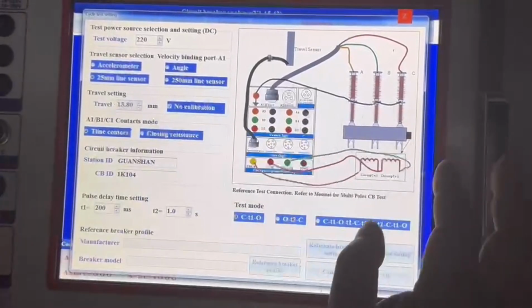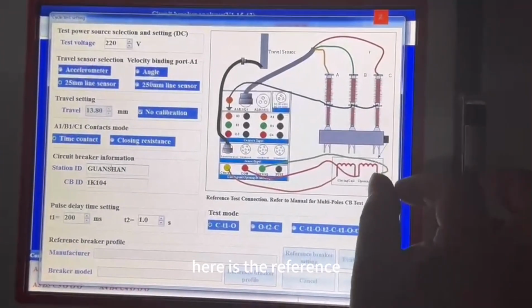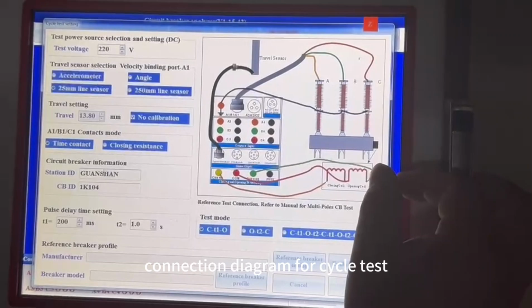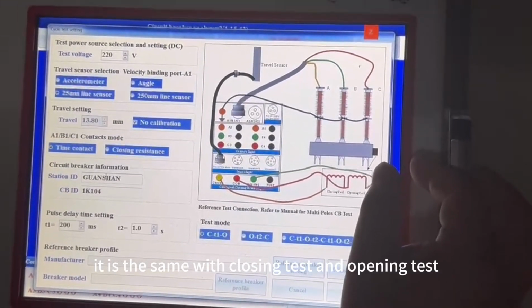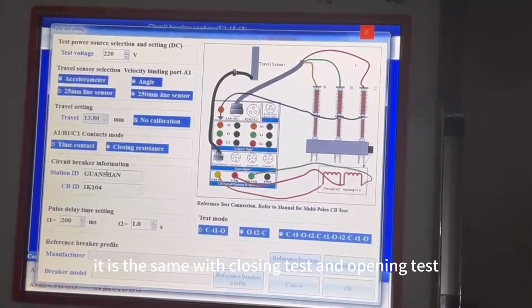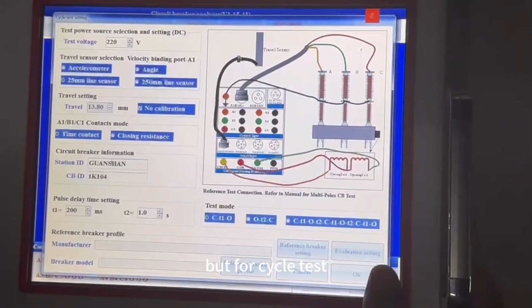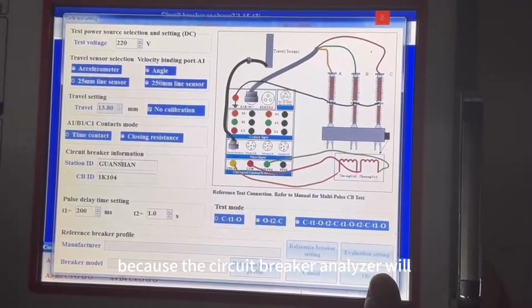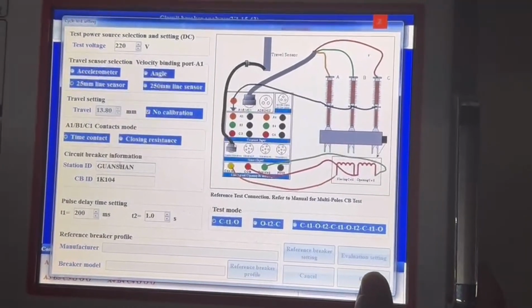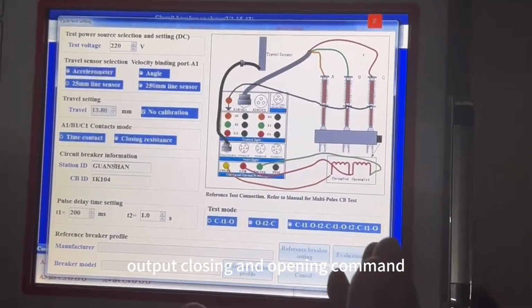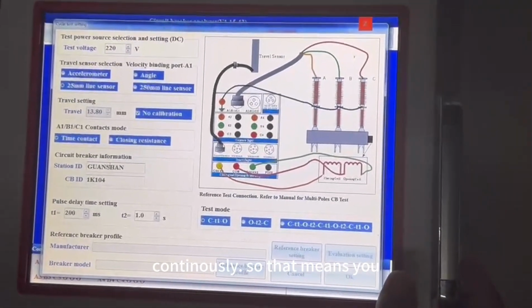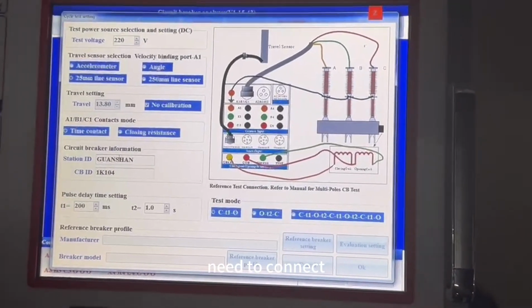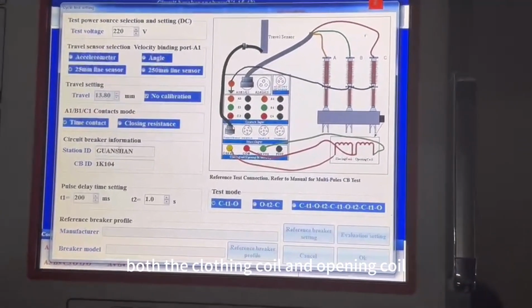First, here is the reference connection diagram for cycle test. It is the same as the closing test and the opening test, but for cycle test, because the circuit breaker analyzer will output closing and opening commands continuously, that means you need to connect both the closing coil and the opening coil.